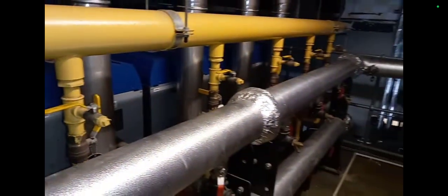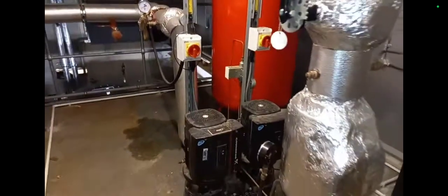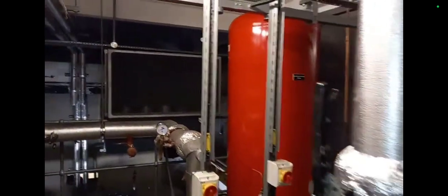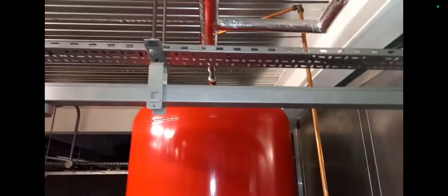And then what else do we have around here? So I think the boiler should be on this side rather than on the other side, but the installers felt otherwise. And then we have a pump here, the main boiler pumps, and then the expansion vessel, and you can see some ventilation over there. And then you've got a pressurization unit there. So heated expansion vessel, quite big.